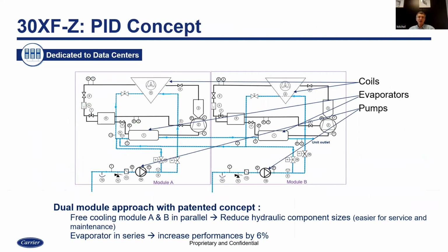So you have the two systems. I said that starting from 700 kilowatts, we have two machines connected together, which makes a larger system. They have two pumps, compressors, evaporators, hydronic coils, etc. And because we have those two machines in series, in mechanical cooling operation, we benefit from a 6% efficiency improvement versus operation in parallel. So this is the percentage which I was saying is for free when you put the units in series in a smart way.